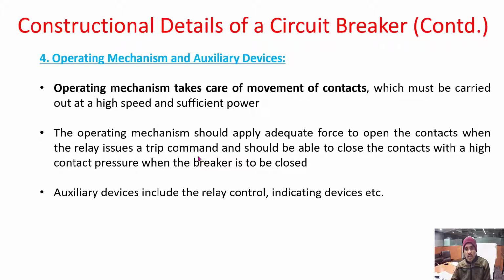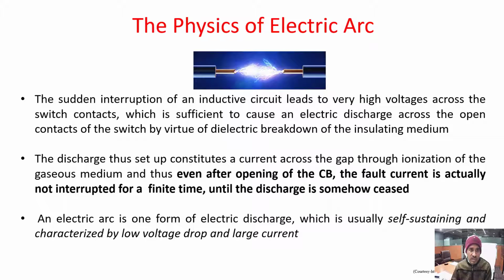So how does a circuit breaker operate? A circuit breaker operates based on the relay command, which will issue an opening command and a closing command. The circuit breaker should be able to do it. So the operating mechanism should be capable of delivering adequate force to open the contacts when the relay issues a trip command, and should be able to close the contacts with a high contact pressure. Because if there is no adequate contact pressure, then there will be contact resistance, which may result in temperature rise or failure of the breaker. So this is how the operating mechanism should work. The auxiliary devices include relays, control, and indicating devices, etc. So these are the main parts, or main constructional details, of a circuit breaker.